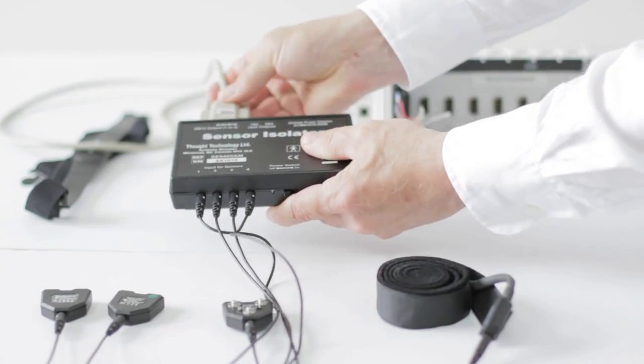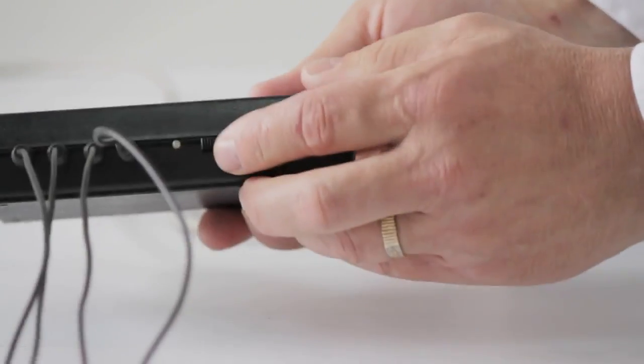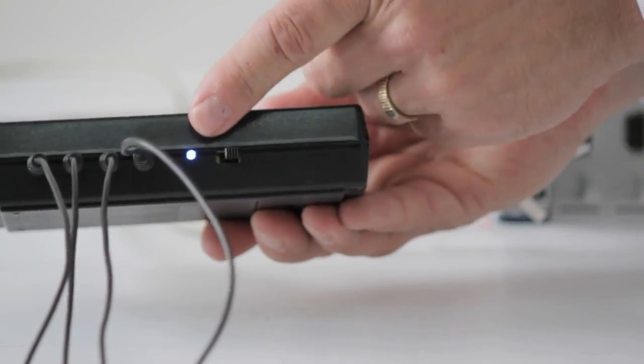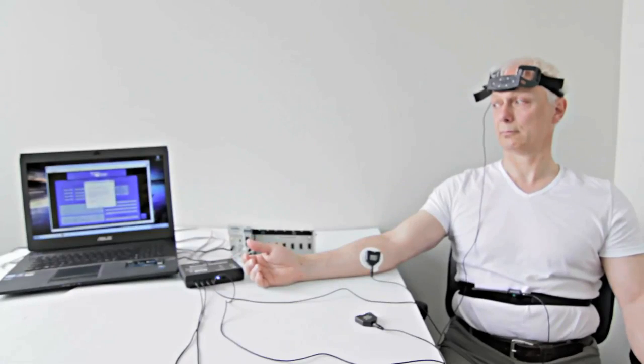Connect the DAC to the isolator. Turn the DAC on and now turn the sensor isolator on to supply power to the sensors. Connect the sensors to the body.